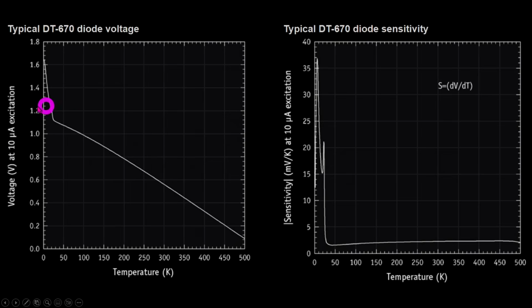Now you can see the excitation current here is kept pretty low. These plots are from a product, the DT670, which is from Lake Shore Cryotronics. These guys are masters at making cryo temperature measurements and building these kinds of systems. The excitation current is kept very low because you don't want to dump a lot of power into the diode, because of course it's going to change its temperature. I don't know what the excitation current of our instrument is, but we can measure it. It's pretty straightforward. And then we can identify a diode and fool the system into thinking that it has the diode that used to be inside its own chamber. And then we can close the loop with it. Yeah, it's pretty nice to see that this is possible.